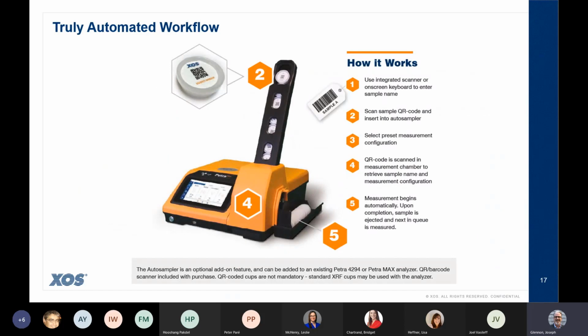Truly automated workflow is how it works. You can use an integrated scanner we have in the software, or you can use the on-screen keyboard to enter the sample name, scan the sample QR code, and insert it into the Autosampler. And then you select the preset measurement configuration. The QR code is scanned in the measurement chamber to retrieve the sample name and measurement configuration. And then the measurement begins automatically. And when it's over, the sample is ejected and the next sample in the queue is measured.